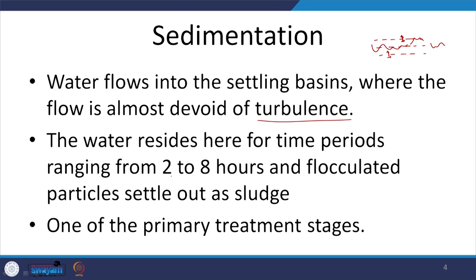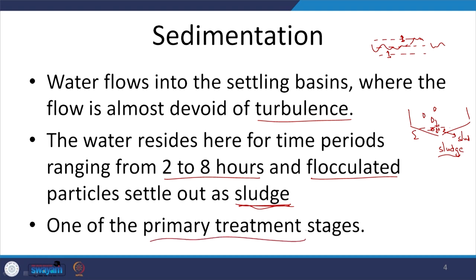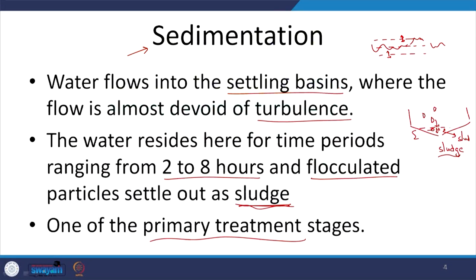Typical retention times are from 2 to 8 hours. The particles or flocs settle out and that is what we refer to as sludge. In the sedimentation basin, the bigger particles settle down and the settled-out fraction is called sludge. This is one of the primary treatment stages. Here we are talking about settling basins only, not necessarily coagulation or flocculation, which are added as and when needed.